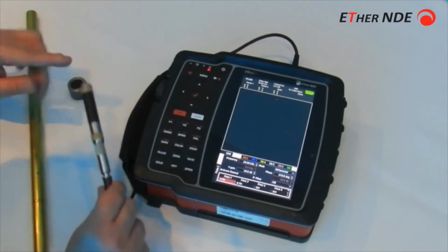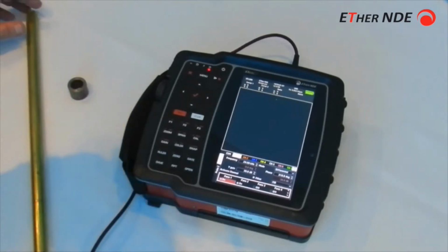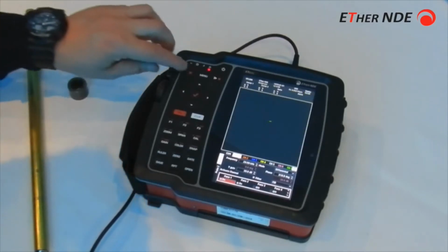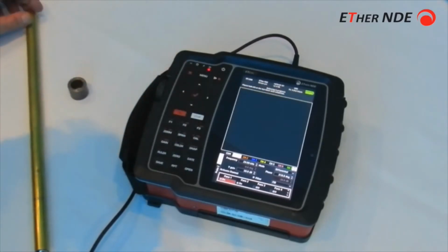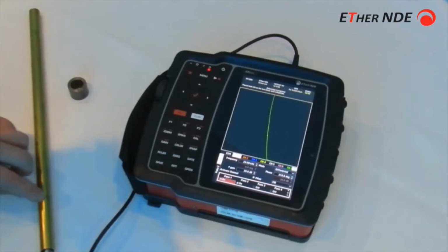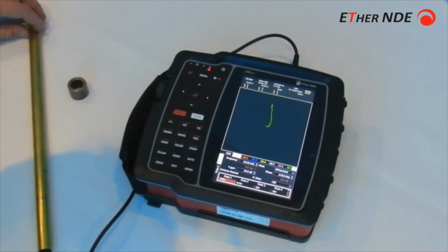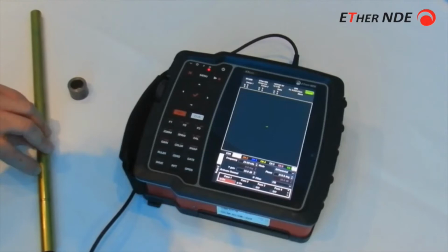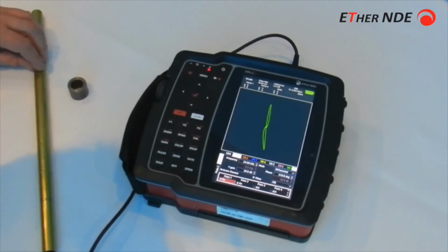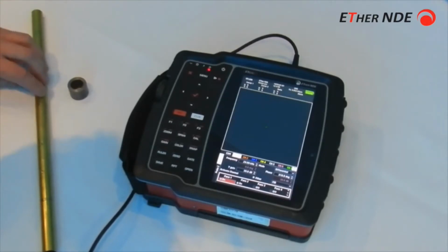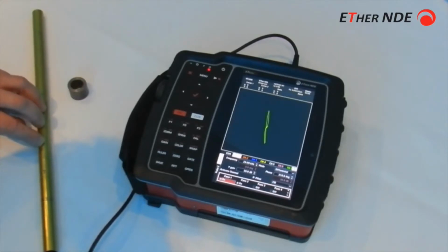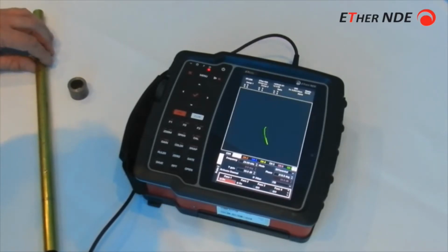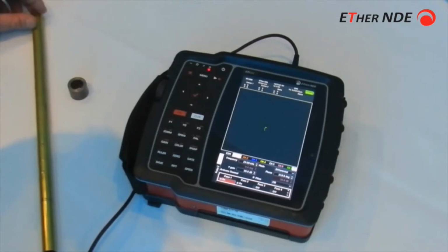The probe is set currently to 20 kilohertz in bridge. If I place it into the tube, find somewhere to balance, press the balance button, and let's go through the tube. There's a big, large 20% OD groove on the outside. It's off screen, but not to worry about that. There's some 20% flat bottomed holes here, and 20%, 40%, 60%, 80%, and then there's a through hole.